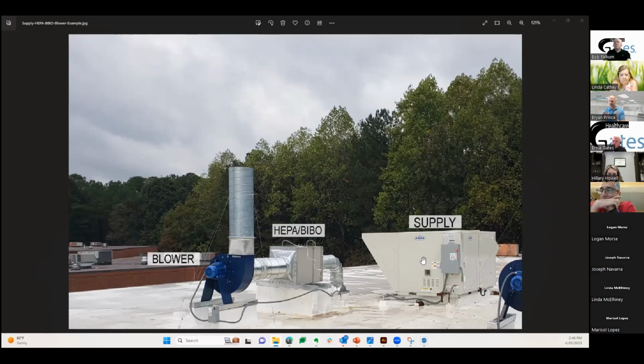They're going to look at you like you're crazy, because that is truly the bottom end of a DX system. And this is still a DX system, but it has modulating or dual compressors. This is the money maker, money breaker. You can buy an $18,000 single stage system, and in July and August your clean room is going to fall out of specification. Or you spend $50,000 on a modulating dual compressor, reading temperature and humidity as independent variables, and you've got an uptime of 99% throughout the year in your clean room.